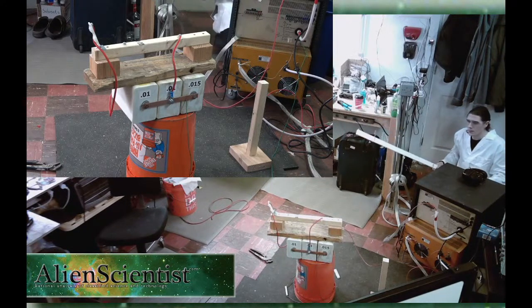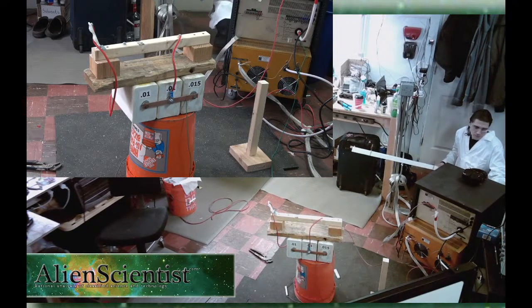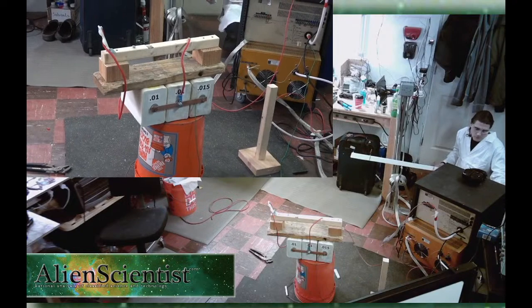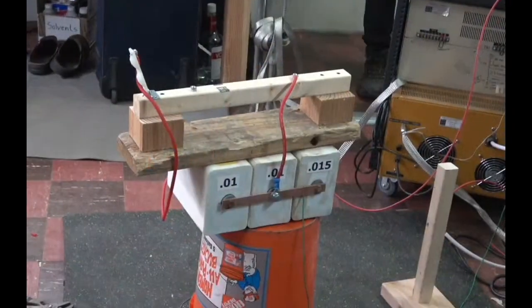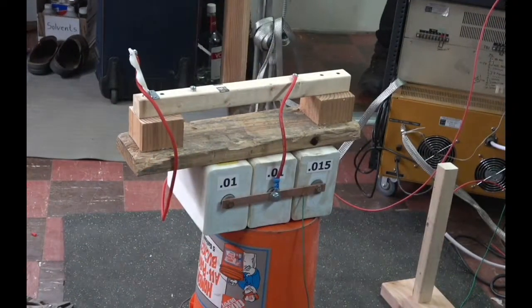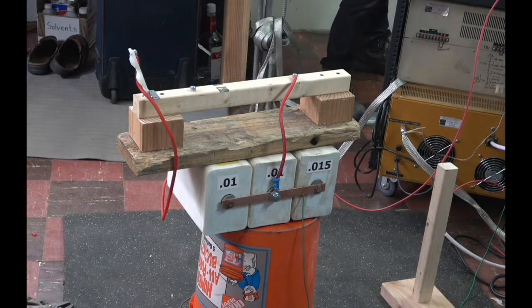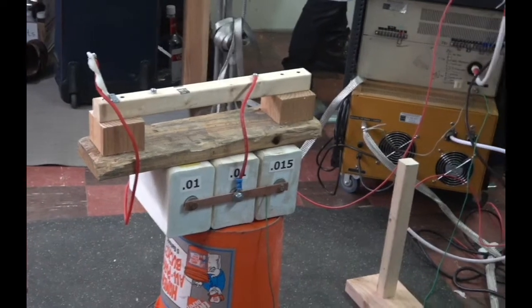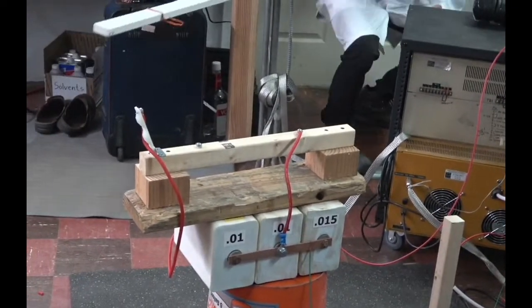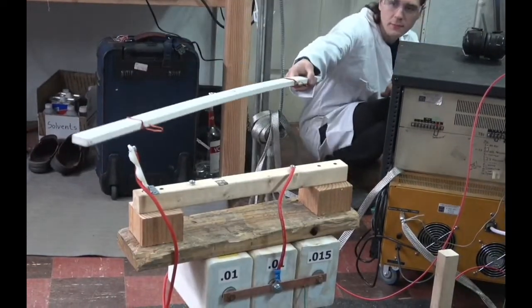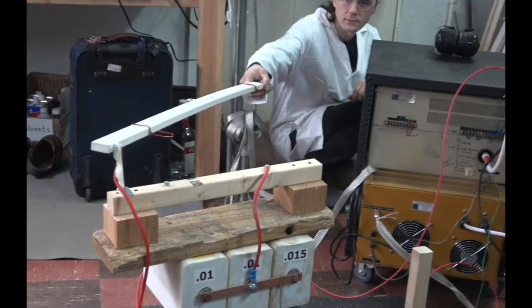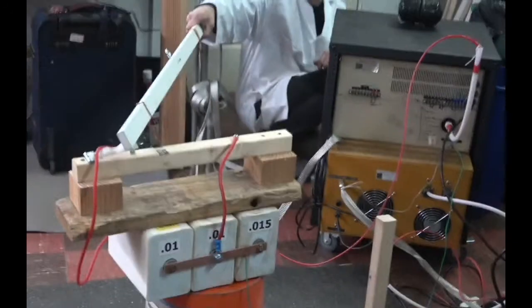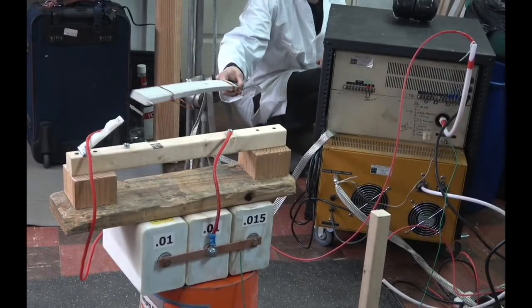Alright, I'm going to leave the high voltage power active. I have it set on the overload setting, so when we trip the power supply it should shut off. This wire is likely to become vapor. Jeremy, we're going. Yep, I'm ducking. There you go. No, it just blew the end.